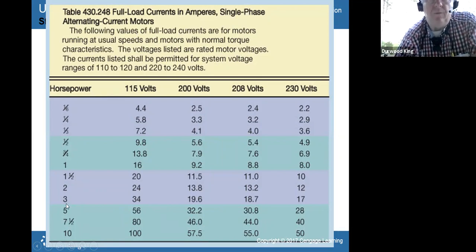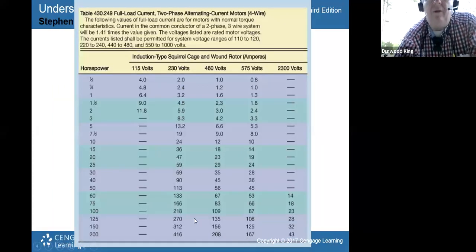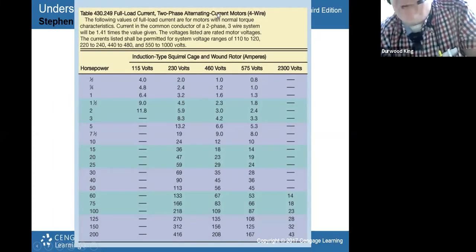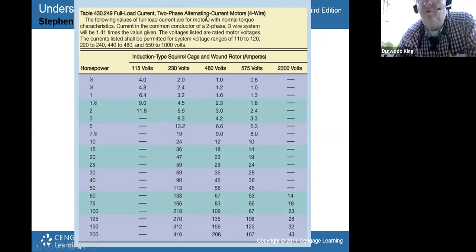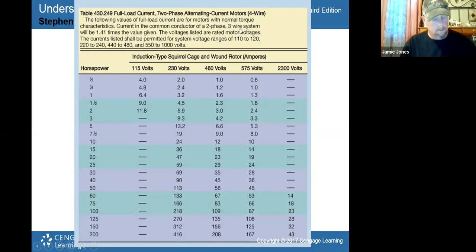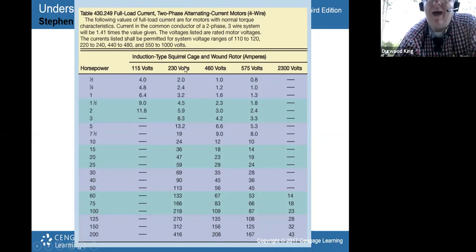These are your horsepower and your voltage columns. At whatever voltage you're running at, you follow it down, and wherever they intersect is going to tell you the amp draw for the motor for a given horsepower and a given voltage. And this is one that I've never had to use. It's on 2-phase AC motors. Actually, they say 2-phase 4-wire. I was thinking 3-wire, but it's 4-wire. 2-phase 3-wire system. But anyway, I've never seen one in a plant.